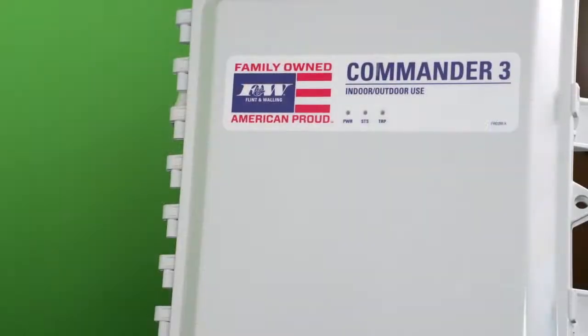The 3-wire Commander 3 drive, now that's going to operate, and I'm sorry, I don't know if I mentioned horsepower on that Commander 2. That Commander 2 will operate everything from a half to a 1.5 horse 2-wire motor. Whereas the Commander 3 will operate everything from a half to a 2 horsepower submersible motor, and that can be either single phase or 3-phase. And the nice thing about these Commander 2 and 3 drives is they're going to virtually run anybody's motor. So that's also a plus side there.